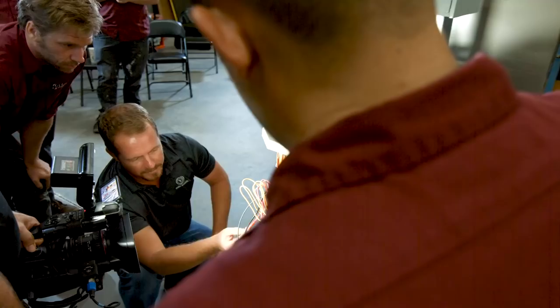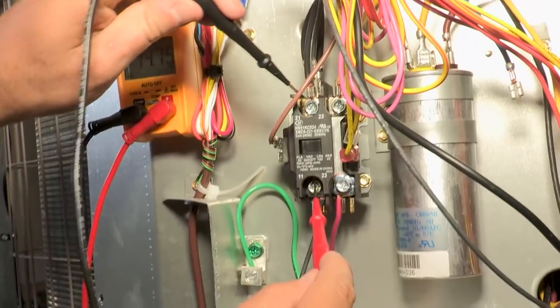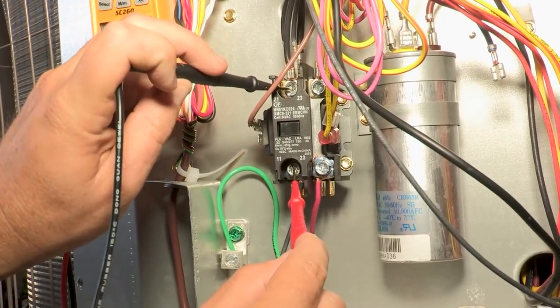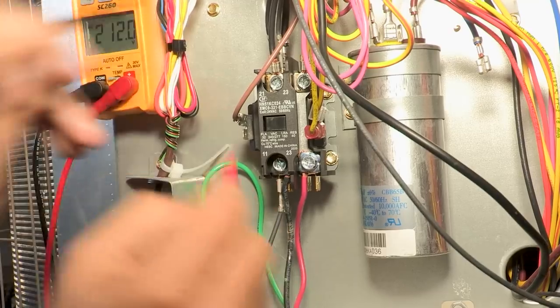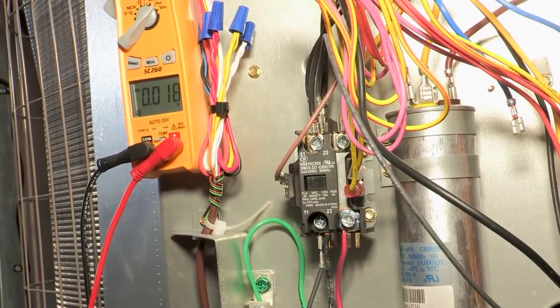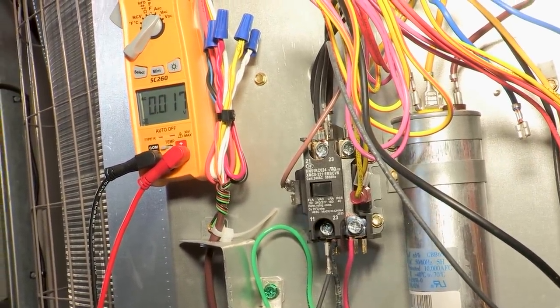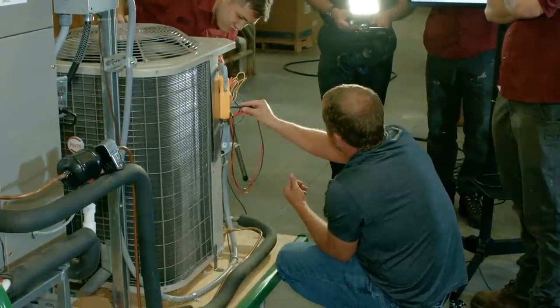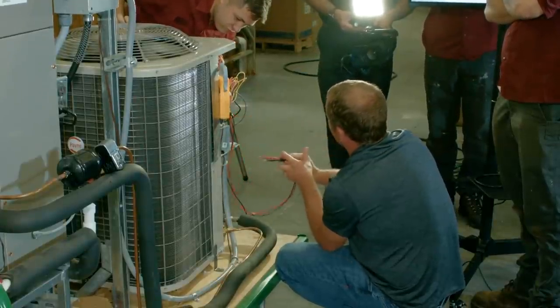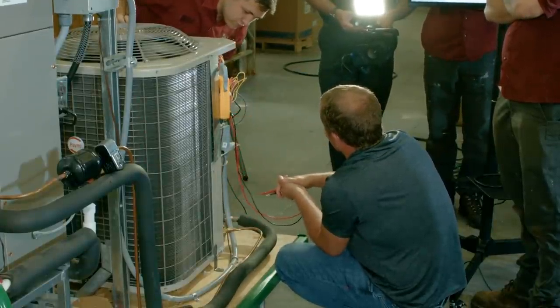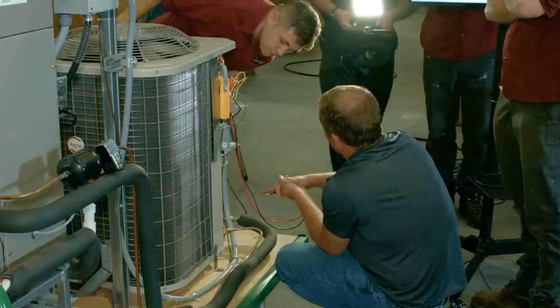But why would we have potential in between 11 and 21? And as you can see, we do. We have 212 volts there. Why would we have 212 volts across an open contact? Because again, we're relying on this to energize our crankcase heater when the compressor is off. We don't want it to be on when the compressor's on.